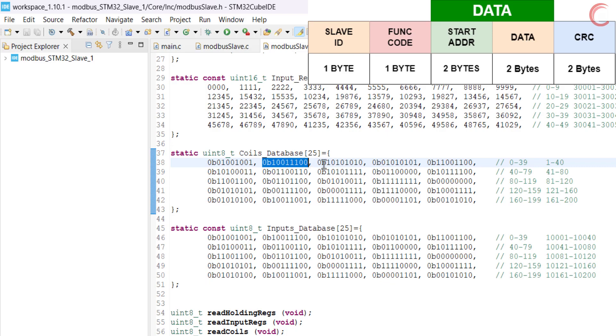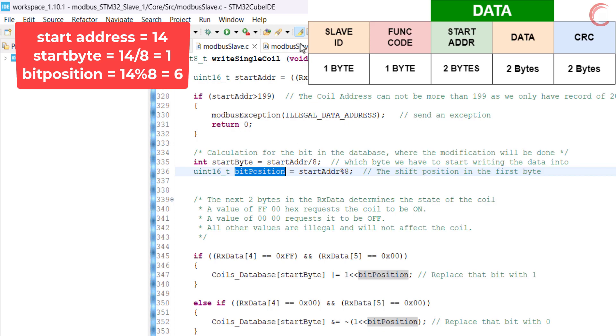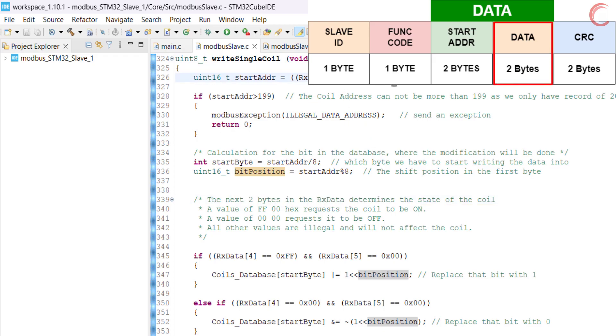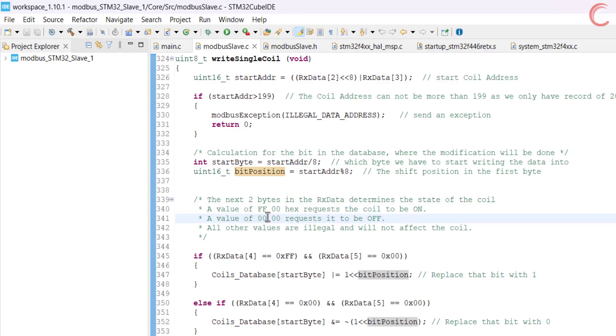Here each byte contains 8 coils. Next we will calculate the bit position, which is the shift in the start byte. For example, if the master wants to modify the 14th coil, then the start byte will be 1 and the bit position will be 6. Next comes the data bytes — the master sends 2 data bytes. If the data bytes are 0xFF followed by 0, that means the master wants to enable the coil. Similarly, if the data bytes are 0 and 0, that means the master wants to disable the coil.